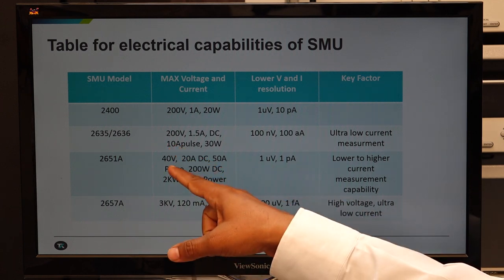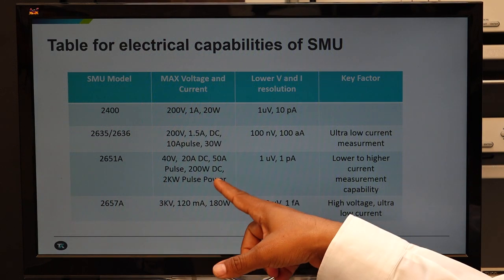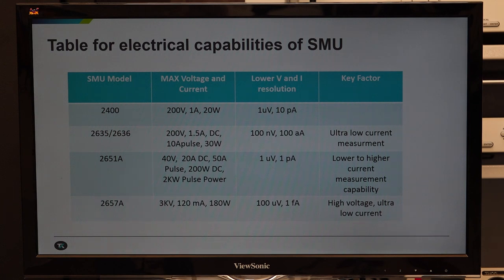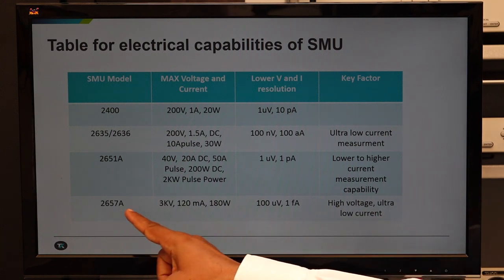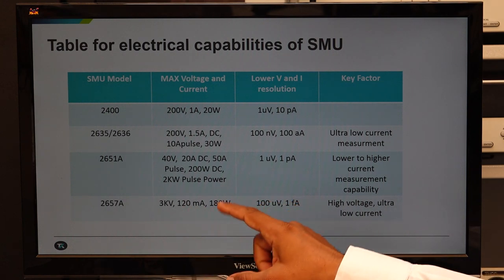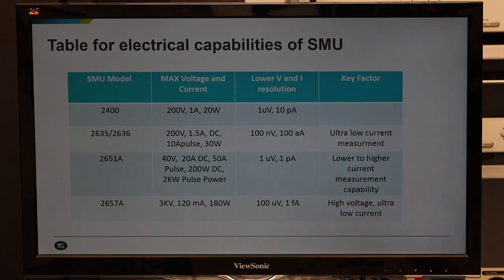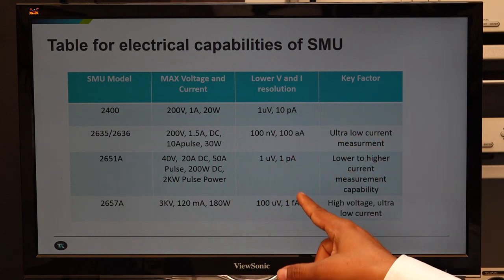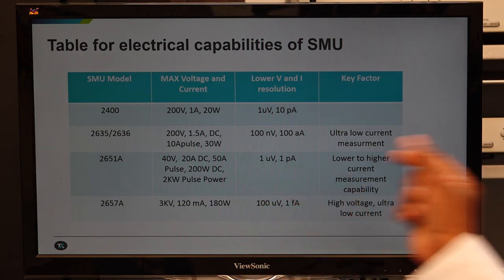Two boxes of the 2651 SMU can be integrated together to double the power from 40 volts to 80 volts, or double the current from 20 ampere DC to 40 ampere DC and 100 ampere pulse for devices needing very high power. For high voltage breakdown testing, we have the 2657A offering 3 kilovolt voltage capability, 120 milliampere current capability with 180 watt power, and 1 femtoampere current measurement range — very useful for testing high breakdown devices for very low leakage current.